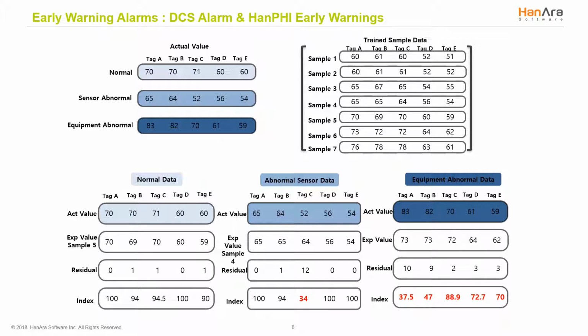When the prediction model is executed, the real-time values are compared with expected values to calculate the residual. The difference is expressed as an index from 0 to 100%, and the greater the difference between actual and expected, the closer to 0 the value. Again, information is useless if it's not easily accessible or understood. So this easy-to-understand health index gives all levels of the organization a better understanding of the current plant status.